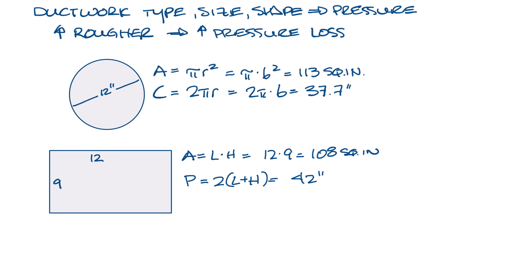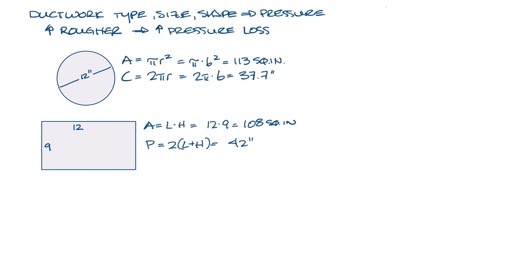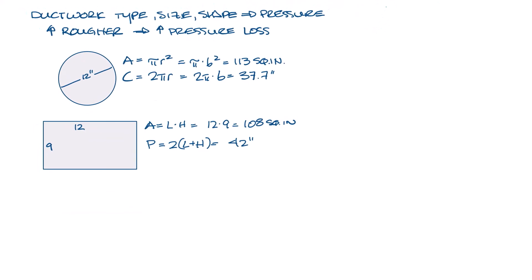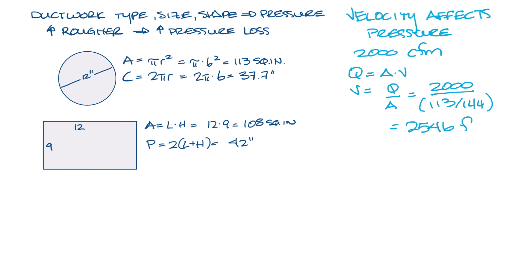The velocity of the air as it passes through the ductwork affects pressure drop as well. We can calculate the velocity and therefore pressure loss for a 2000 CFM in this 12 inch round duct. So if you remember from earlier videos, q equals area times velocity. So velocity is CFM divided by area. So that's 2000 divided by 113 square inches and divide that by 144 to convert that to feet. And we have a velocity of 2546 feet per minute.